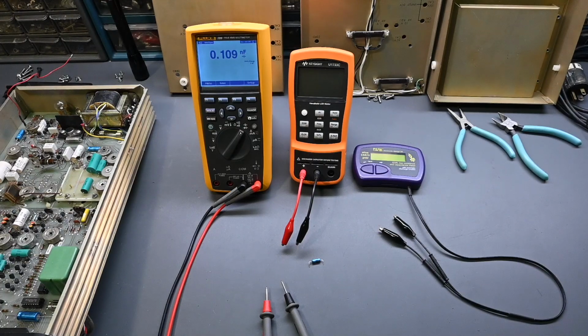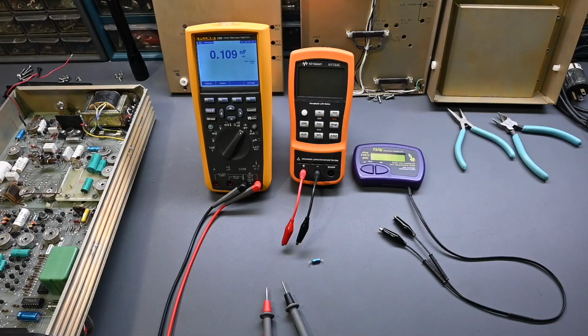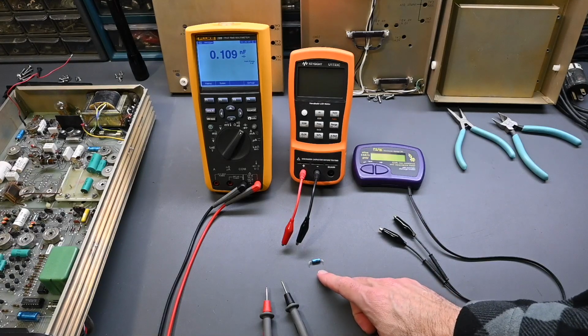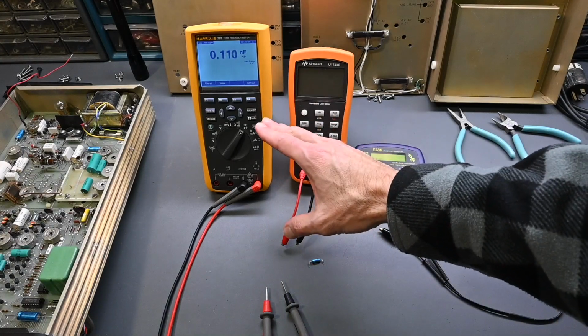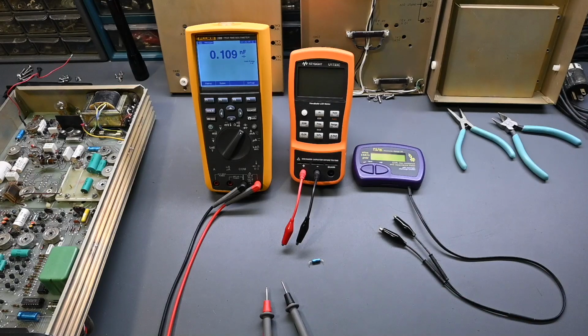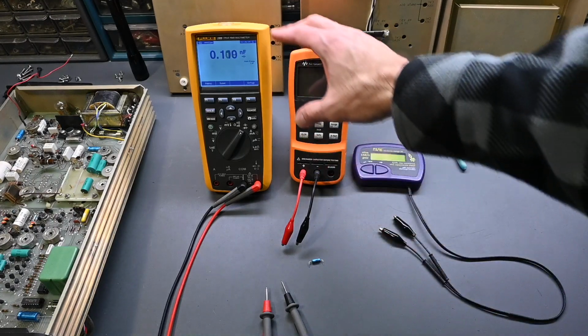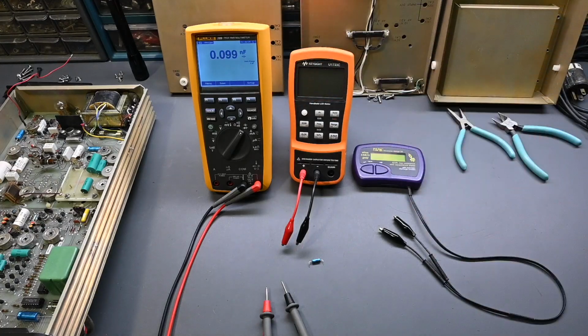We don't know anything about the ESR or the leakage. There's also another test on the Sencore, the dielectric absorption test. So obviously some more tests can be done, and there's no way you can do that with a digital multimeter. But keep in mind, if you take a reading on the capacitor and it's suspiciously high in value, perhaps many times more than expected, that's a sign the capacitor is becoming very leaky.